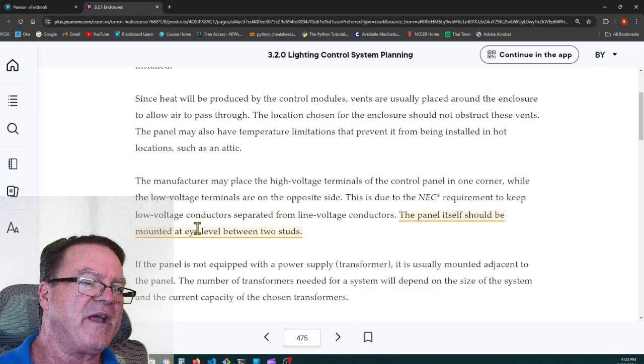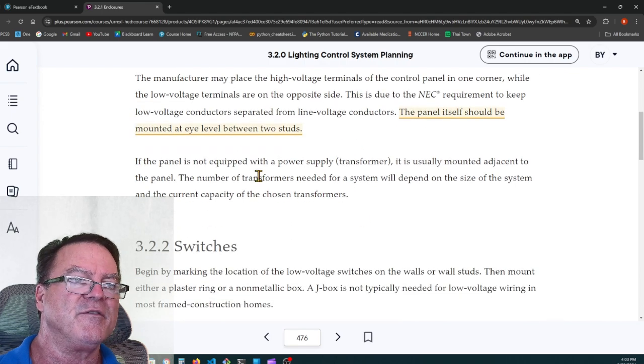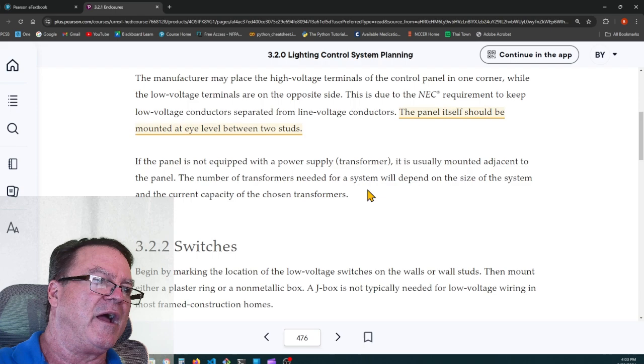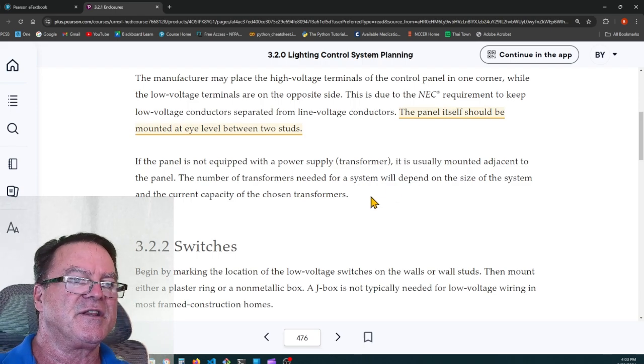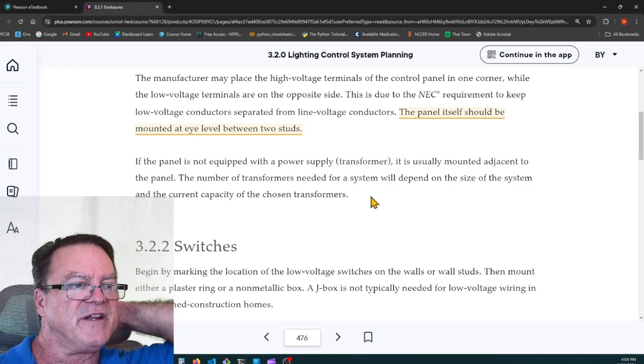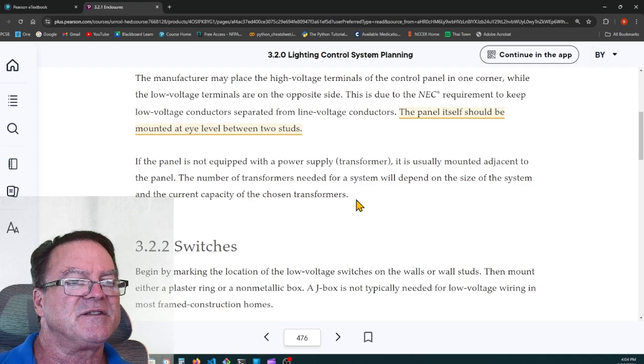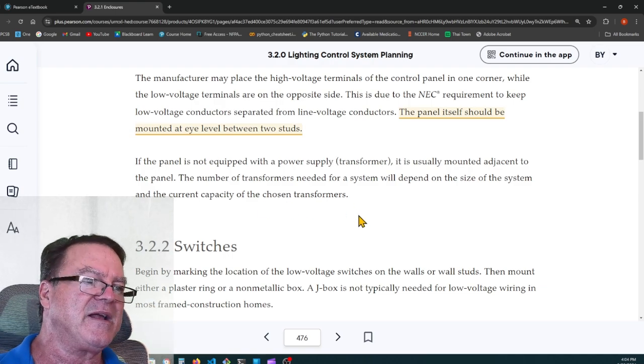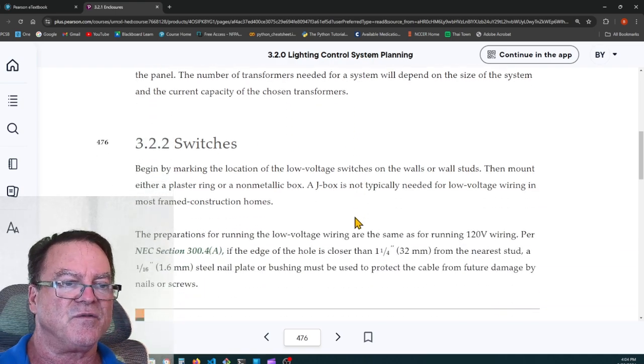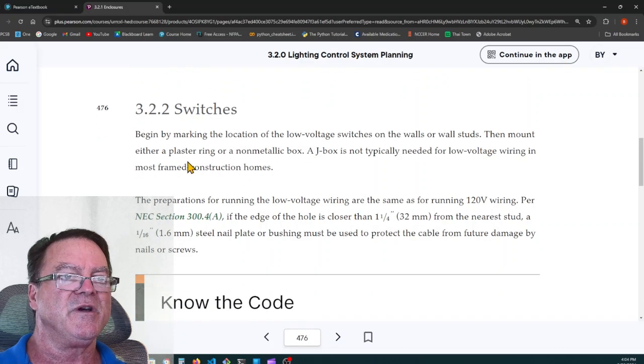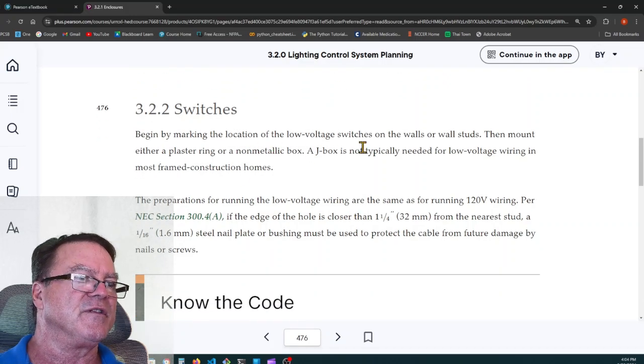The low voltage panel should be mounted at eye level between 2 studs. The panel is not equipped with a power supply. It's usually mounted adjacent to the panel. The number of transformers needed for a system will depend on the size of the system and the current capacity of the chosen transformer.